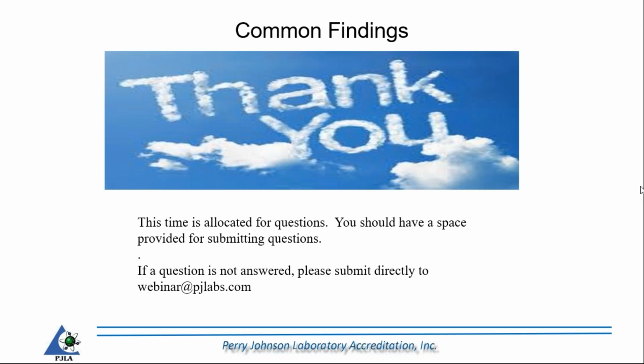For labs that develop an LDT test with no PT available, is prior approval required to do intralab precision? Yes, it is. So again, if you want to pursue intralab or repeatability studies, you would contact PJLA headquarters. As stated earlier, you need to state your case. You need to state why interlab or third party is not feasible, and then also how you plan to conduct the intralab proficiency test and analyze the data in a meaningful way.